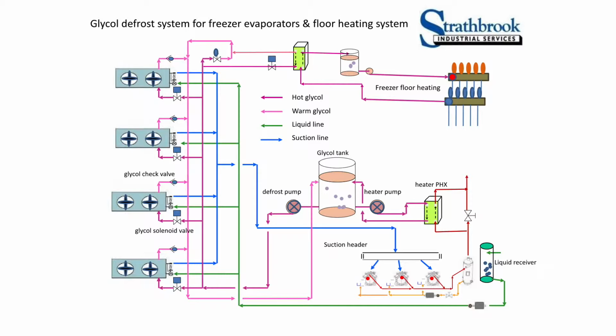recovers heat from the discharge of the R134A system. A pump pumps it out of the glycol tank, puts it through the heat exchanger and back into the tank. We get it up to 50 degrees, and then on demand we start the delivery pump, and the particular evaporator needing to be defrosted turns the fans off. We open up a solenoid and pump 50-degree glycol through dedicated tubes in the evaporator, and that effects the defrost.